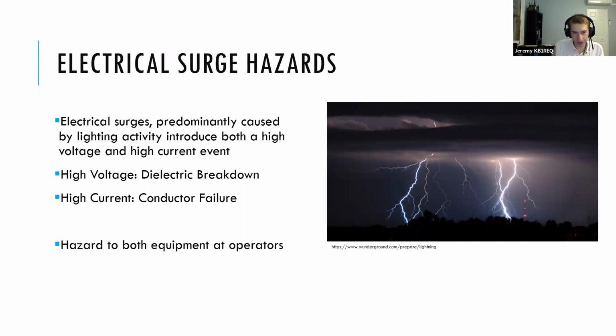We're dealing with a high voltage situation. That means in a surge, you're going to have electrical currents flowing in places that they don't normally flow. Things that are usually preventing electricity from flowing between two points, when we're dealing with lightning and a voltage that high, don't do that job of holding off voltage. And of course, the currents we're dealing with are extremely high. Your conductors that normally conduct electricity fine are much too high for them to handle at these current levels. And that's where we see fire and burns, just from that high current. So the combination of those is obviously a very dangerous scenario, because we have a lot more electricity than we're used to flowing in places that we're not used to having electricity flow.